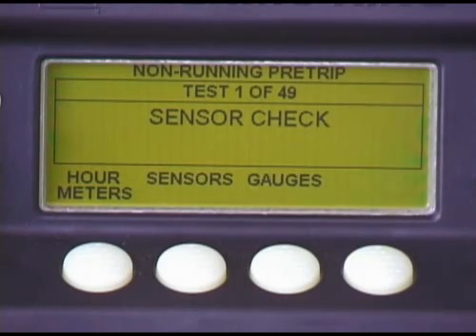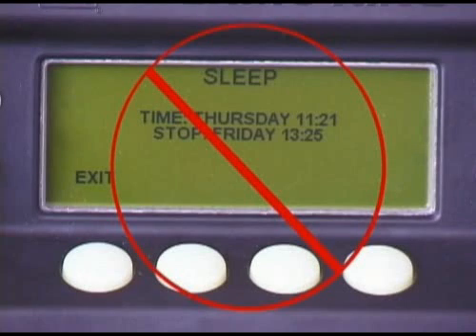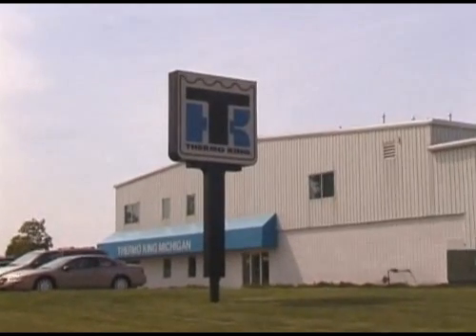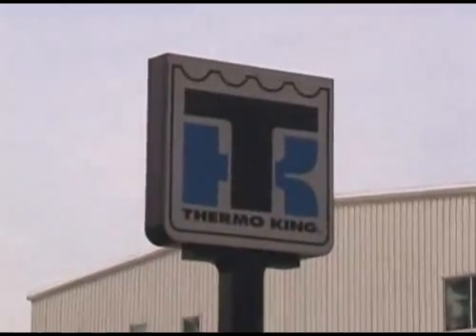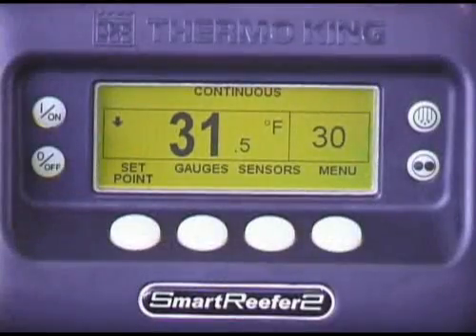Two different automatic pre-trip tests allow you to verify proper unit operation prior to carrying a load. The full pre-trip includes both non-running and running tests. The running pre-trip does not include non-running checks. To successfully initiate either one, there must be no alarms in memory and the unit must not be in sleep mode. If alarms exist that cannot be cleared, contact your ThermoKing dealer for assistance.